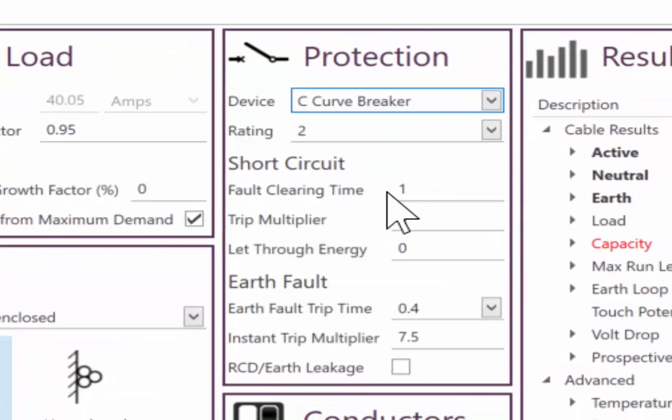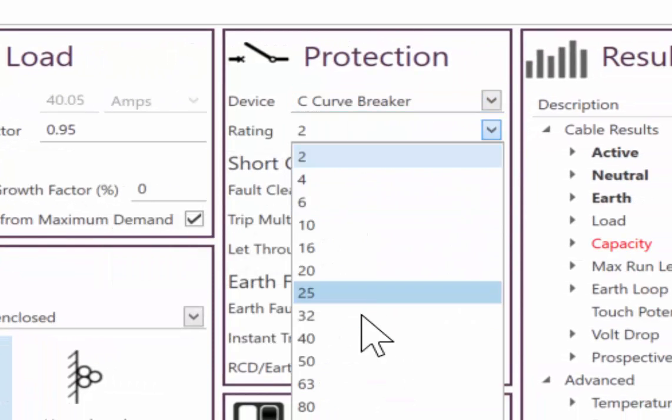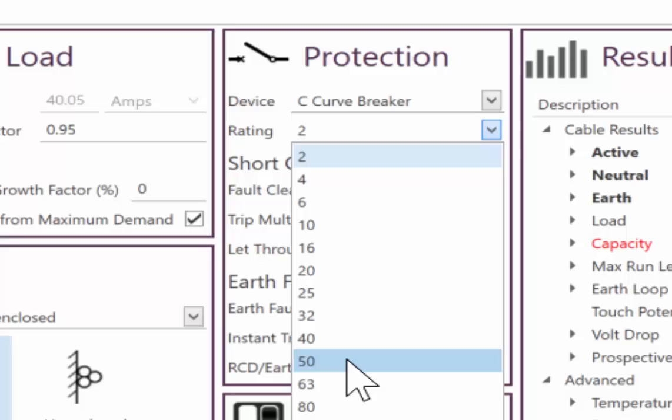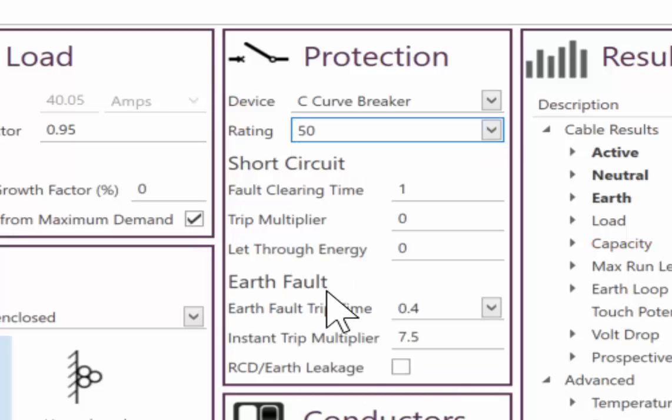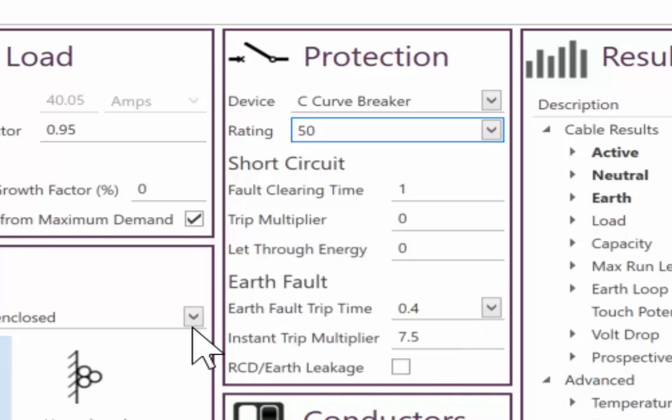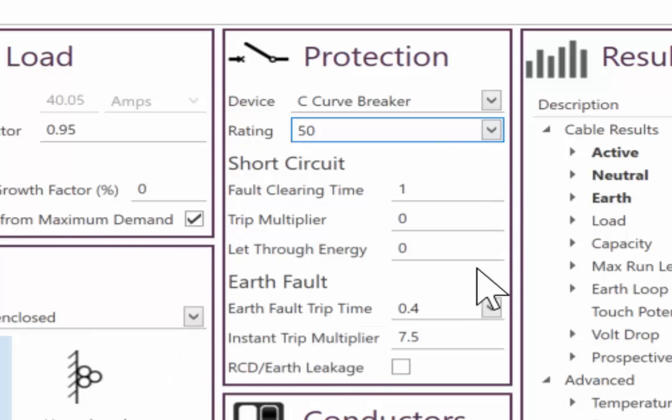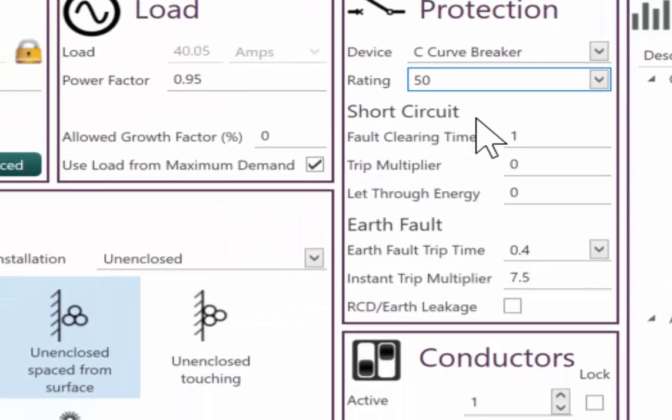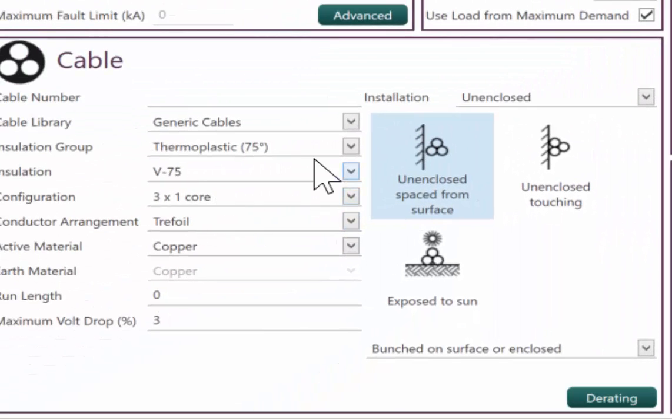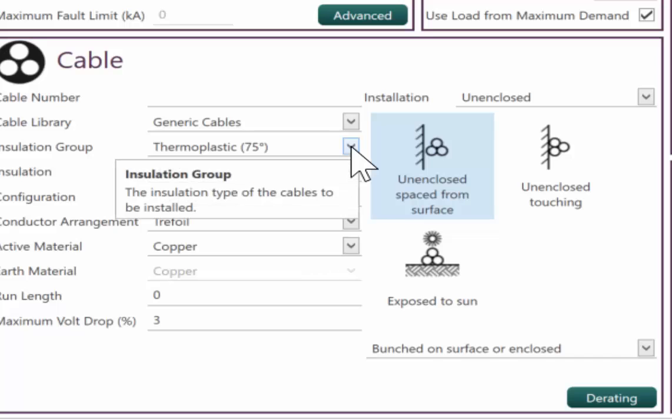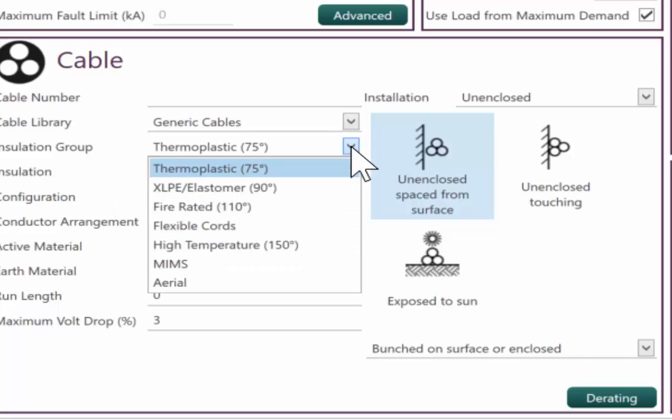Our protection, put a type C breaker. And we'll rate that at 50 amps. You have the option to change your trip multiplier based on standards as you wish. And you can also put in the details of the breaker if you know what they are. So we'll also now go and pick a cable.